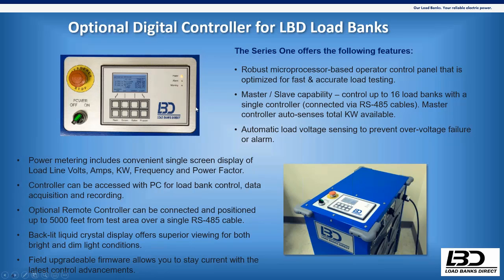As you can see here, it doesn't show the 3-phase meters like you'll see on our standard manually controlled units, but you can get all the same info off the screen of the controller itself. You can also store the test results and download them to a computer, put them in a spreadsheet, however you need to. You can also control them with a PC if you don't want to control them directly from the controller. You can run a cable to a PC, operate them from there, and monitor the load test. Say you've got an 8-hour load test: somebody could sit in their truck on their computer and monitor it, make sure everything's going according to plan, they're getting all the information they want, and the load bank's operational, without having to stand next to these things all day.